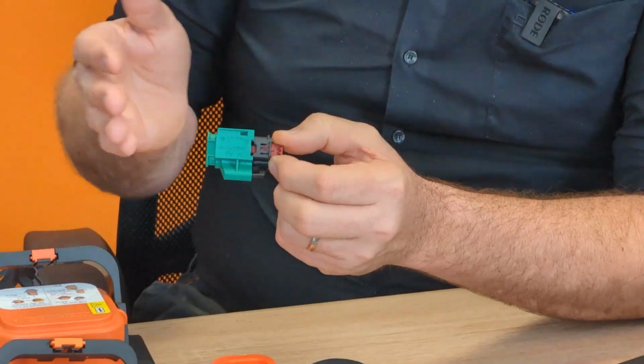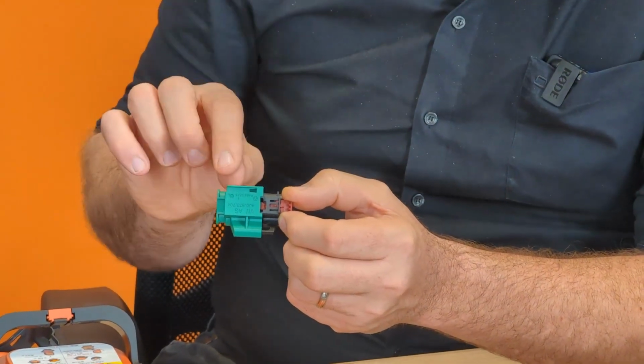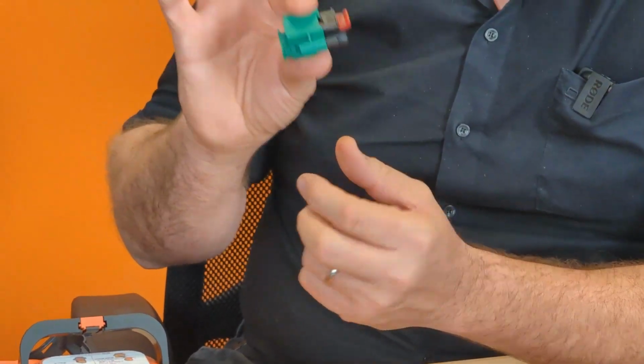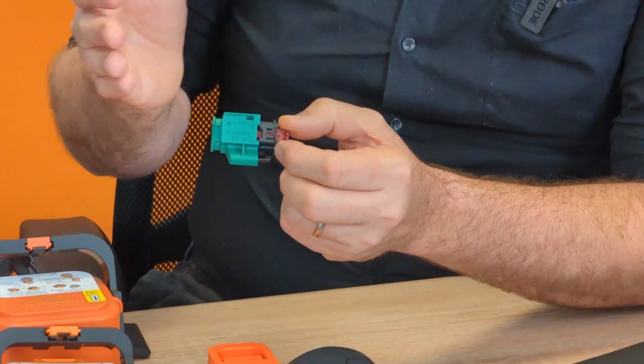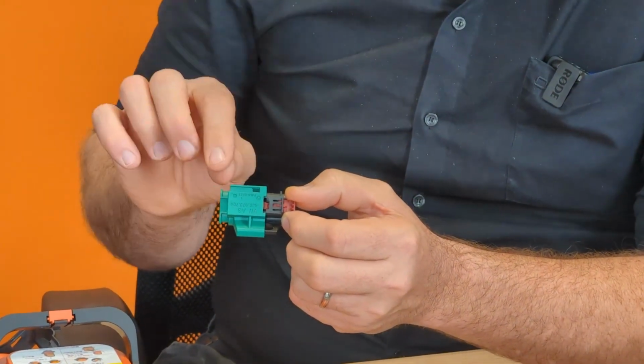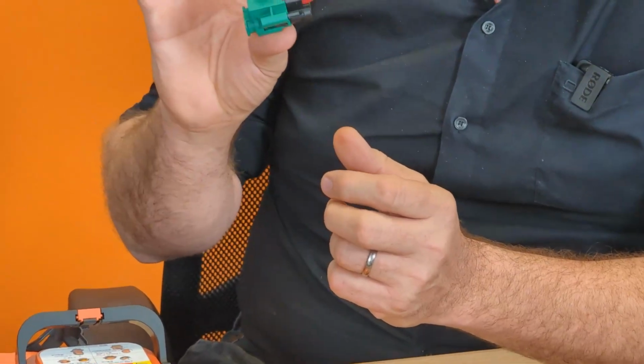So this is just a connection without the cables on it, but what we see now is a low voltage service disconnect. This one here is also part of the interlock, but it doesn't contain the high voltage itself. That's why it's green as opposed to orange.